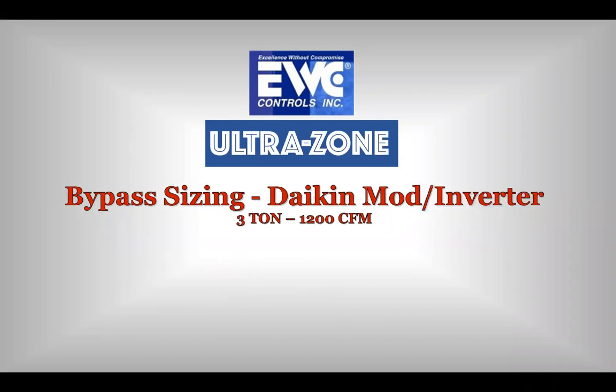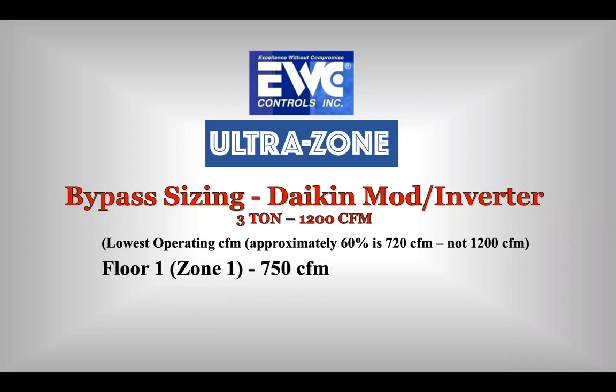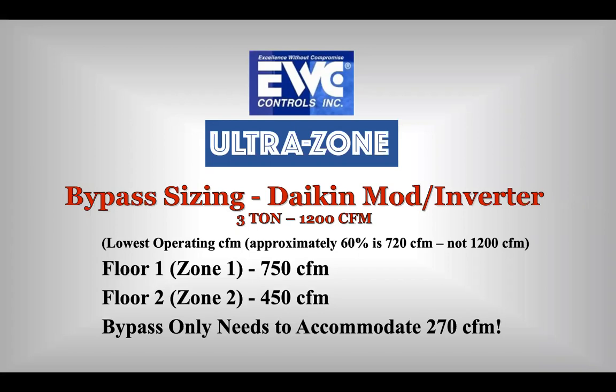If I look at the mod and inverter, and most would like to think that I won't need a bypass, truth is 60% with the mod furnace is the lowest fan operating CFM. With the inverter, I go down to 40, but that doesn't help during the heating mode. So I use 60%, which lowers it to a little bit more than a multi-stage. I'm down to about 720 CFM now. Zone 1, zone 2. Now I'm down to 270 CFM is all I need to bypass.